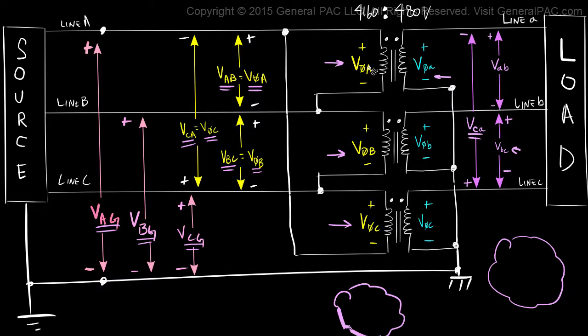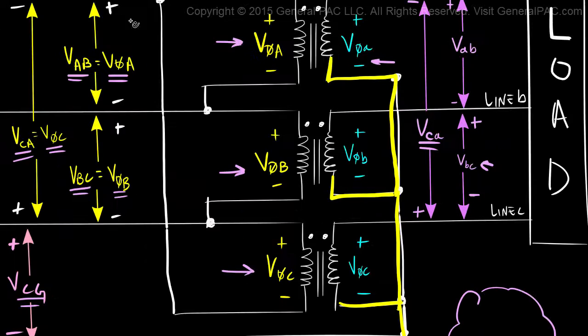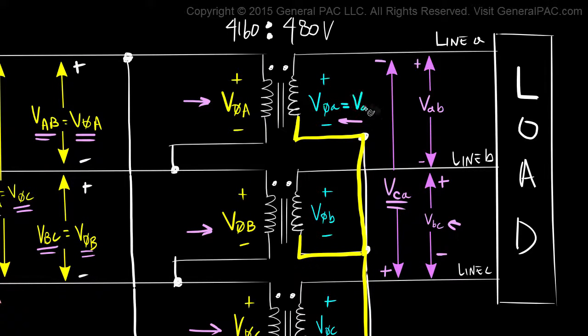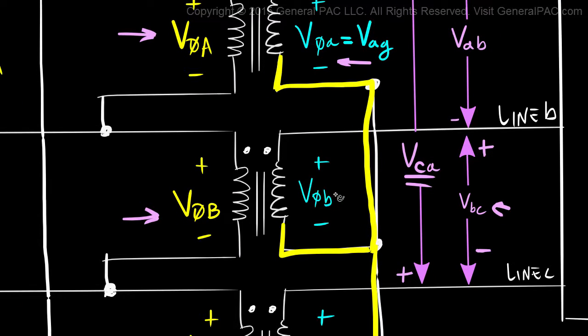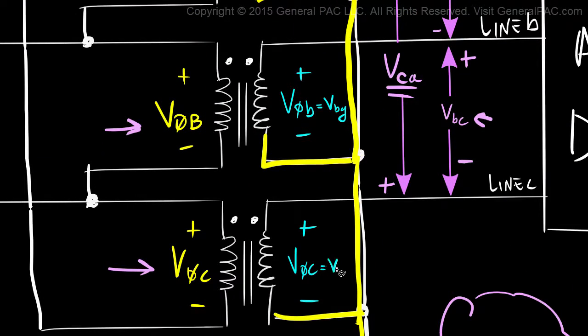Now that we have talked about all of these quantities, let's introduce one more. The low voltage side is connected in Y — and this low voltage side is also grounded — so all of the nonpolarity sides are all connected together and they are all grounded. Which means that we could also label the voltage measured across winding A as VAG, because the voltage measurement is across the polarity side of winding A and to ground. Similarly, we could take the voltage across winding B on the low voltage side and call it VBG, and then lastly the same thing for VCG.